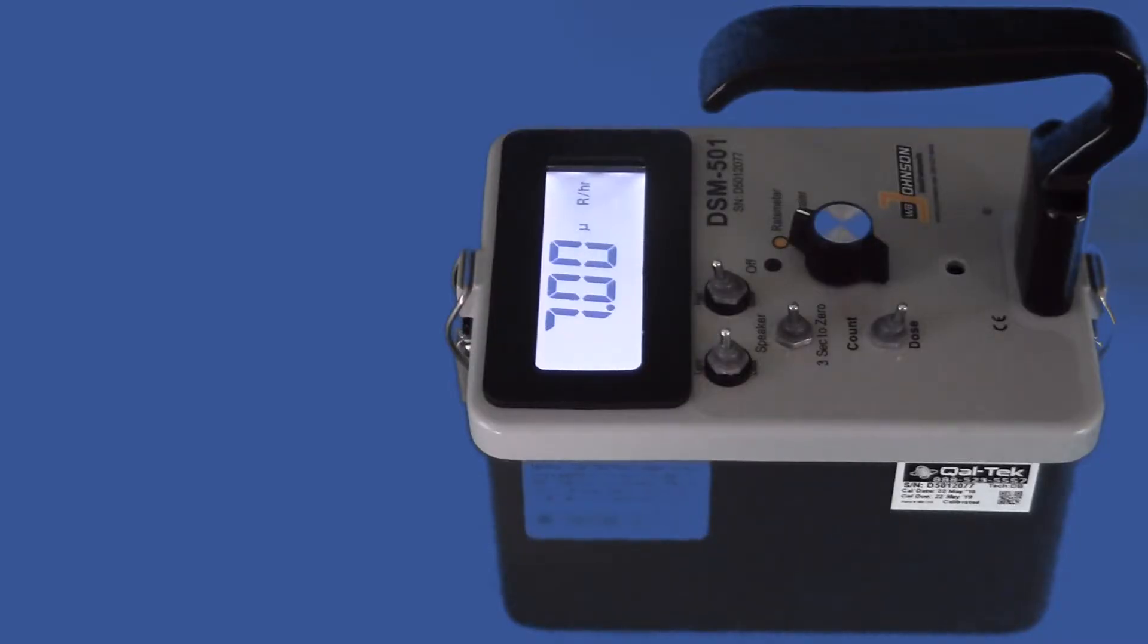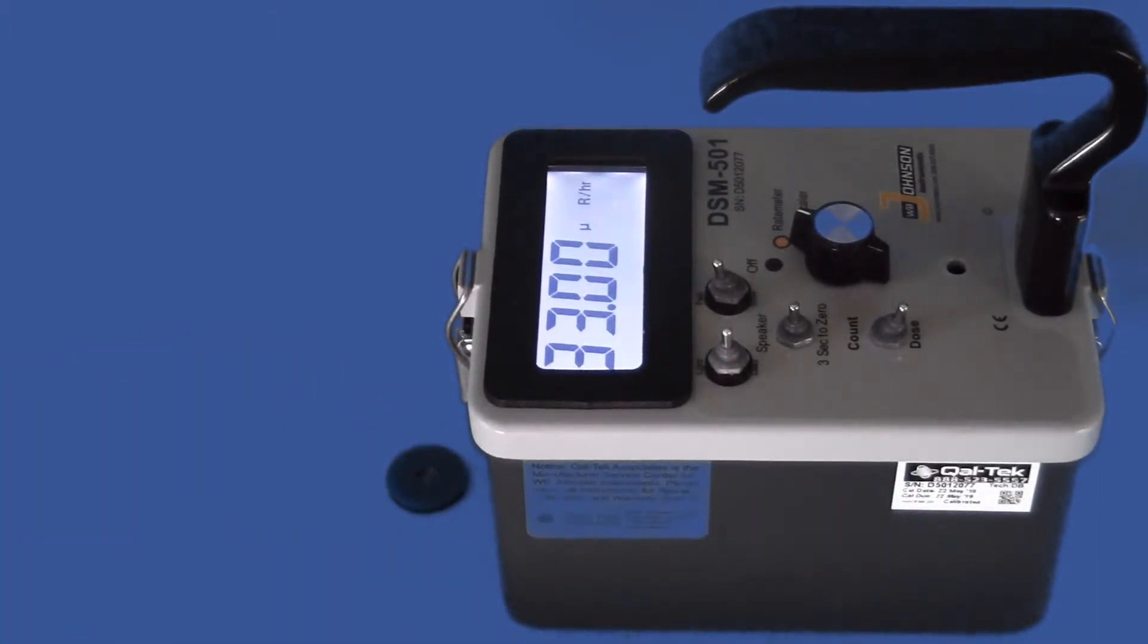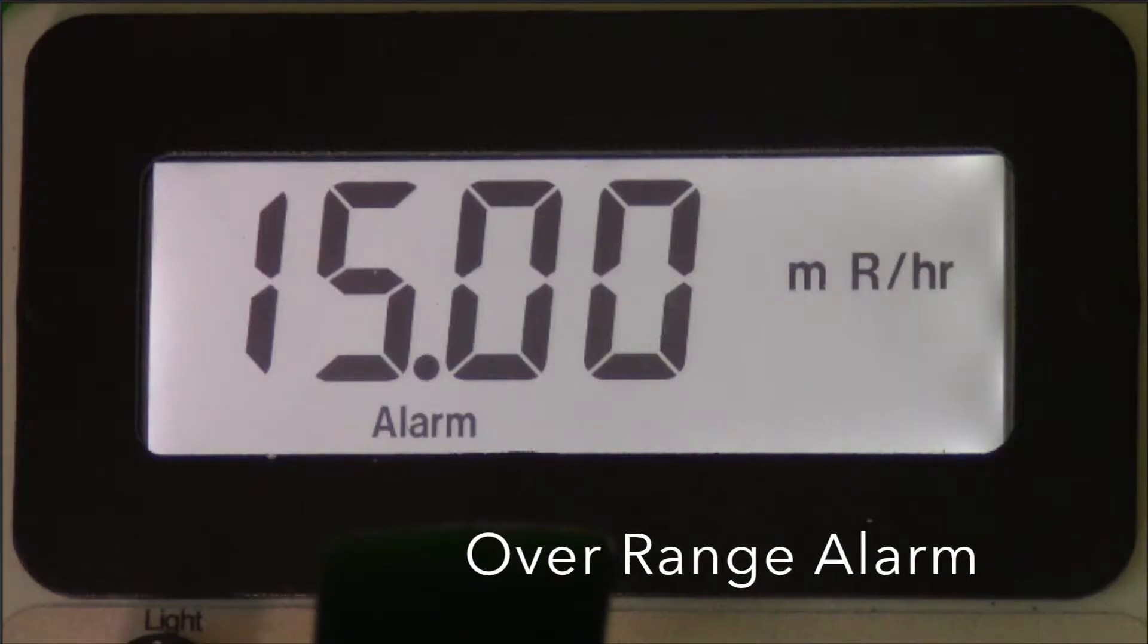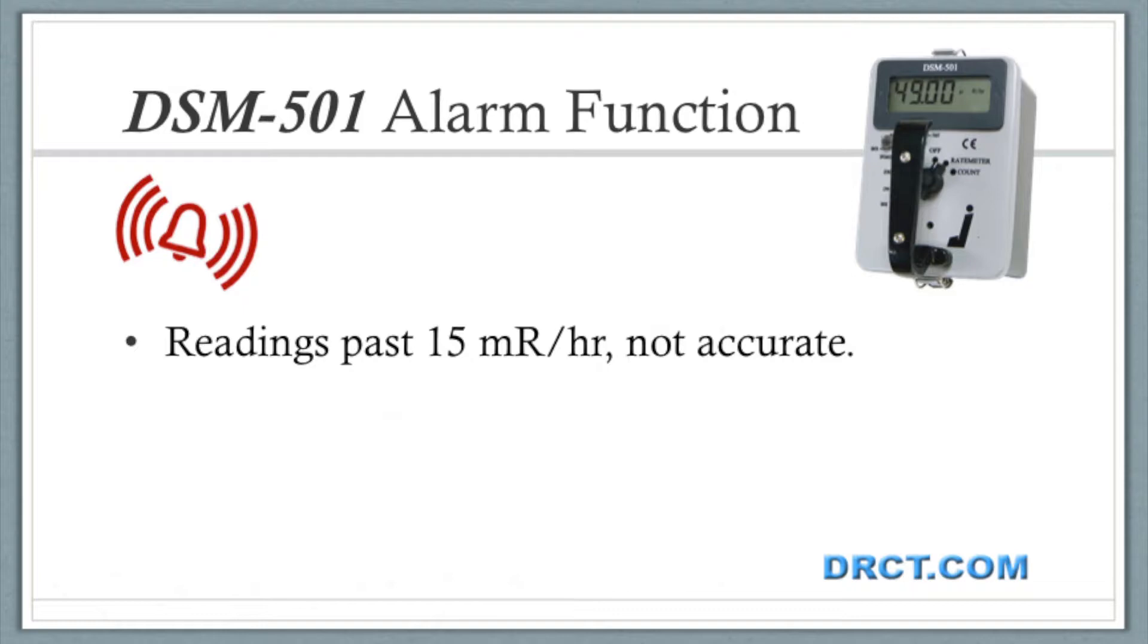We will now test the operational alarm with a weak 1 microcurie cesium-137 source. We won't test the overrange alarm because we don't have a source at hand with a high enough activity. Please note that with readings past 15 milliroentgen per hour, the results are not accurate.